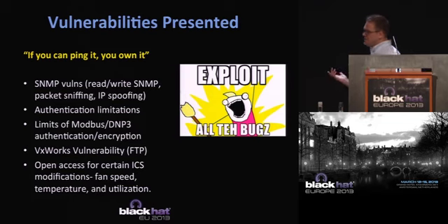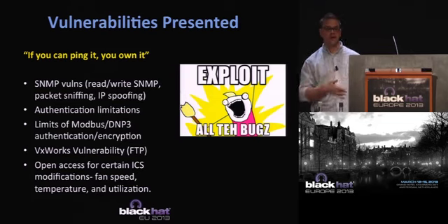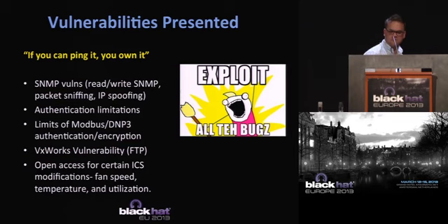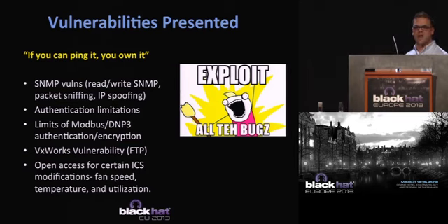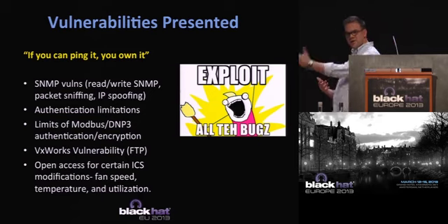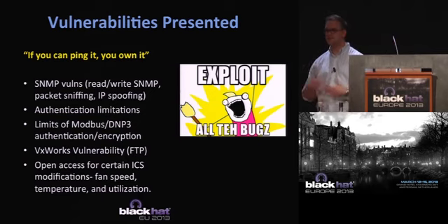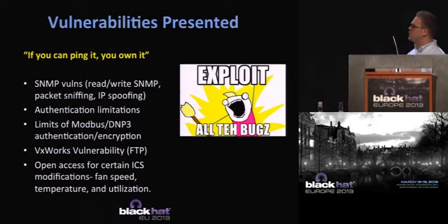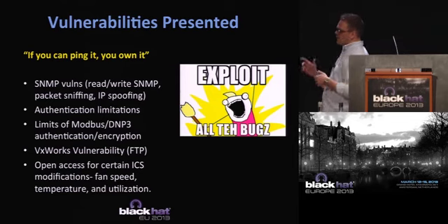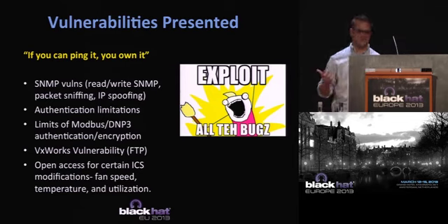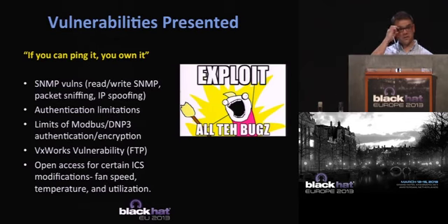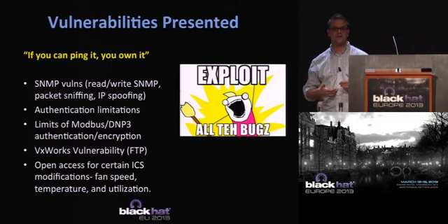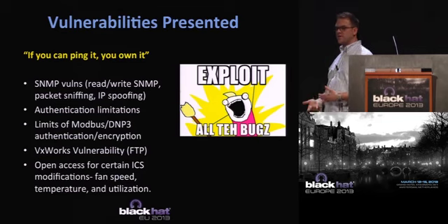I also presented limits of Modbus and DNP3 authentication and encryption. If you remember back to earlier slides, DNP3 and Modbus don't have authentication. They don't have encryption. There are iterations, again, that support those technologies, but in this case, it's not supported. So it's vulnerable to spoofing, it's vulnerable to sniffing the actual traffic, etc. I also presented a VxWorks vulnerability, which is utilizing just FTP, wide open on that, and then I also configured default username, passwords, etc. And then open access for certain ICS modifications. So in this case, it would have been fan speed, temperature, utilization, and containment of the water system.